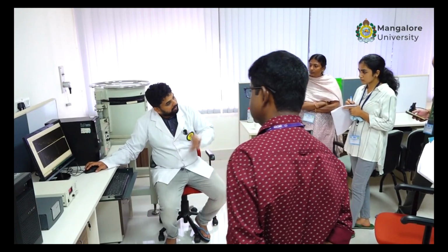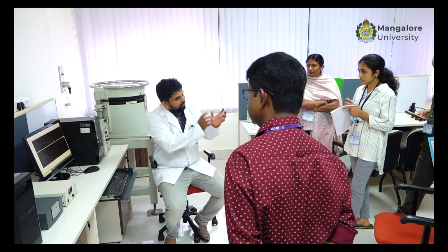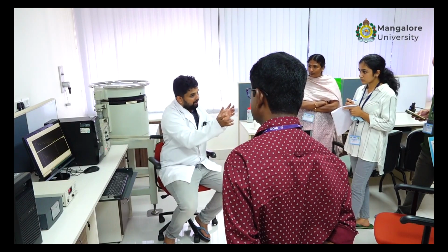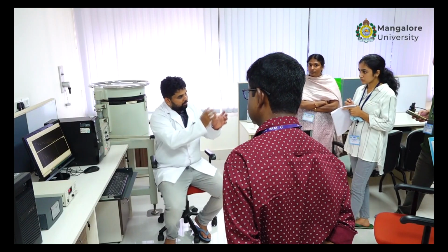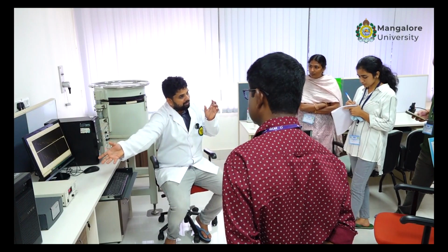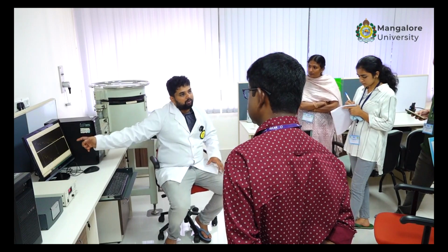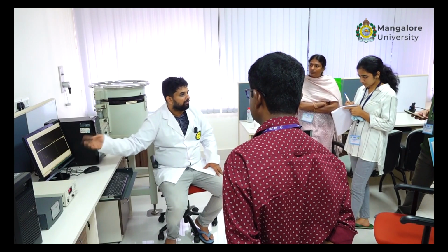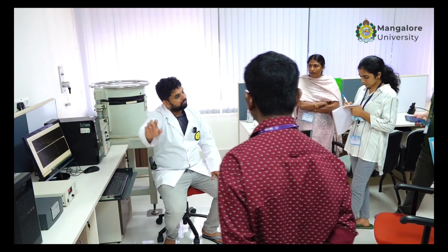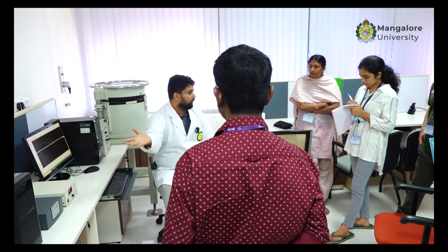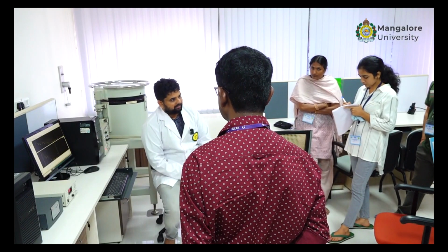Now again, the K-40 peak counts will have some contribution from thallium and also bismuth. So the peaks in front, the higher energy peaks, will always contribute to the lower energy peaks, so we have to make a separate calculation to suppress this. Okay, there that issue is not there. Their Compton correction is done by the PC itself, by the software, so I don't have to worry about Compton correction. Here we have to do Compton correction.